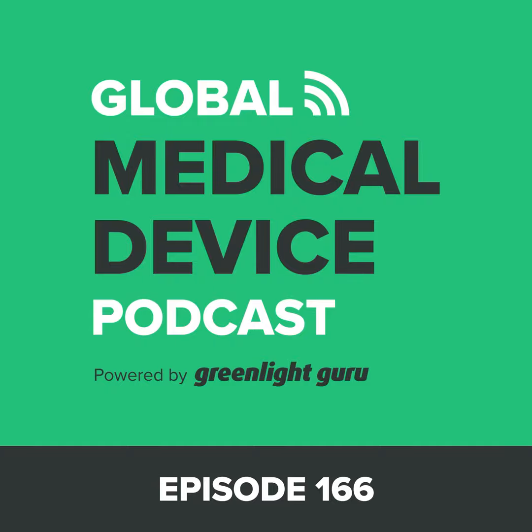I mean, this is a commodity, a material that had been used for decades, and there was a long history of use, and reportedly there was a whole master file with FDA from this particular supplier with respect to biocompatibility, but we still had to go back to the drawing board. So that was a little bit of a head scratcher to me. That's a great example, John. Thank you for sharing that.